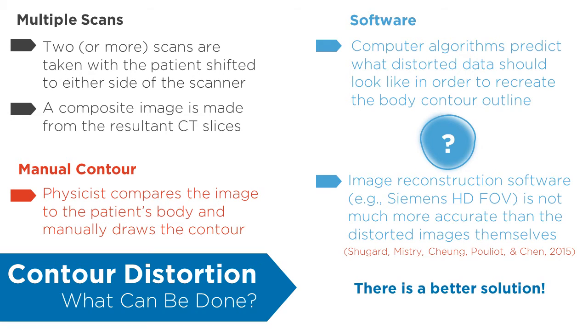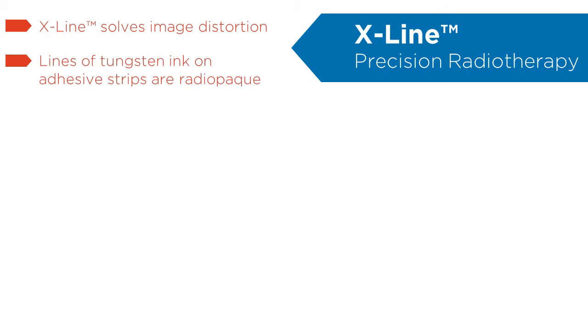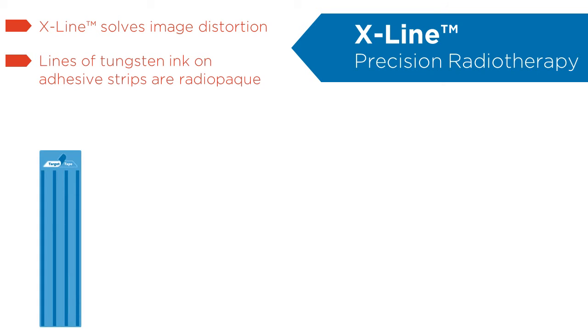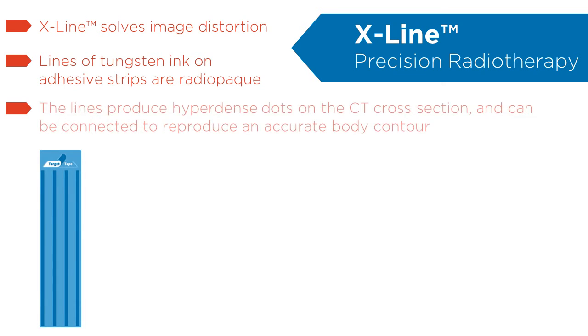Thankfully, there is a better solution. Our X-Line device solves image distortion within the extended field of view. By placing lines of radio-opaque ink on adhesive strips, we are able to provide a series of reliable, hyper-dense dots on the CT cross-section that allow the body contour to be reconstructed accurately.